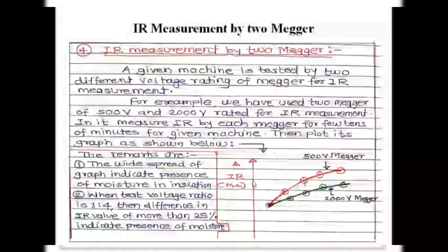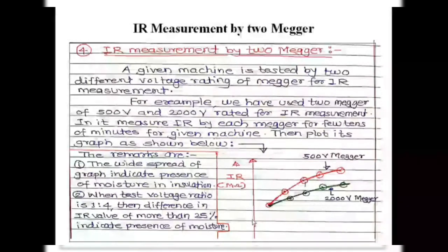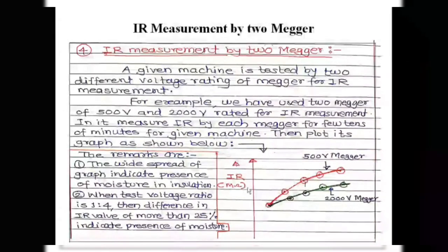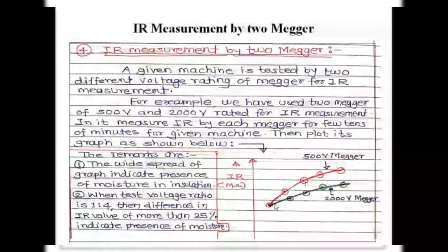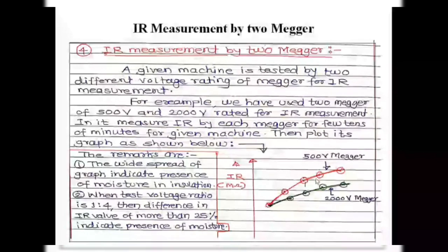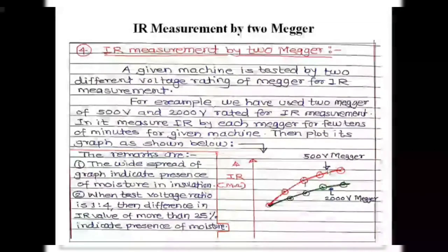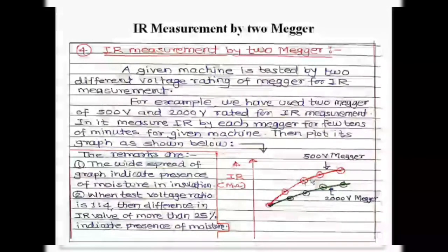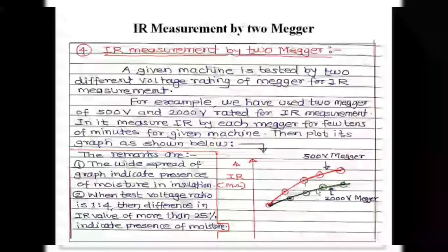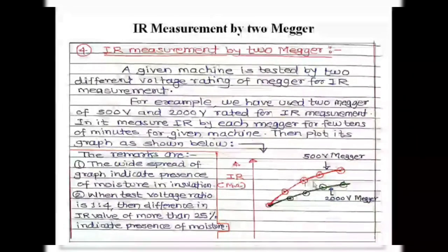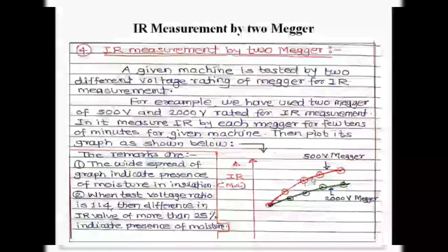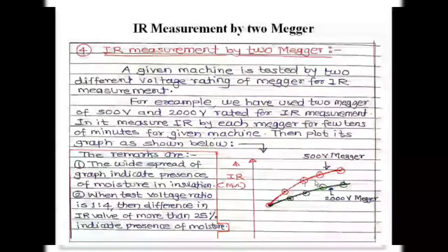The graph is similar to the dielectric absorption curve, with time on the x-axis and insulation resistance in megaohms on the y-axis. The red color shows the 500 V megger reading graph and the green color shows the 2000 V megger reading graph. The first significance of this graph is the spread: if the graphs are closer together, the insulation is in dry condition; if they are more separated, it indicates the insulation has absorbed moisture, solid impurities, dirt, dust, or an oily sticky layer.